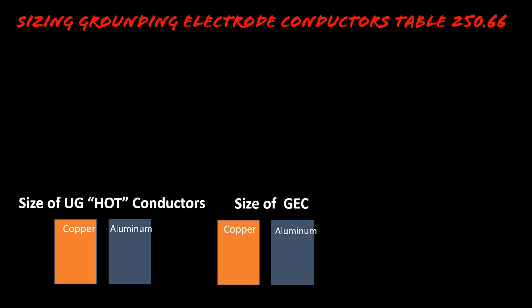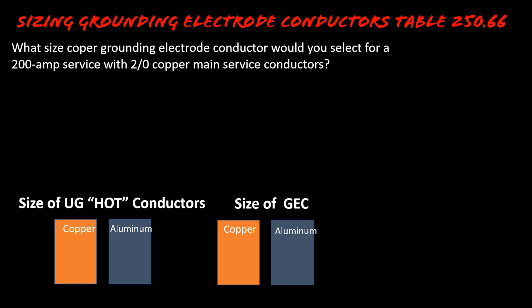Let's imagine that our question was: what size copper grounding electrode conductor would you select for a 200 amp service with 2/0 copper main service conductors? Just a little tip — they put the 200 amp main in there just to throw you off, because when we deal with Table 250.66, it doesn't matter what size the main is. It's sized based off of our 2/0 copper service conductors.